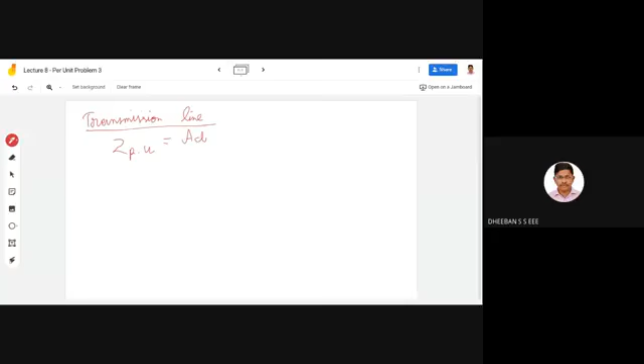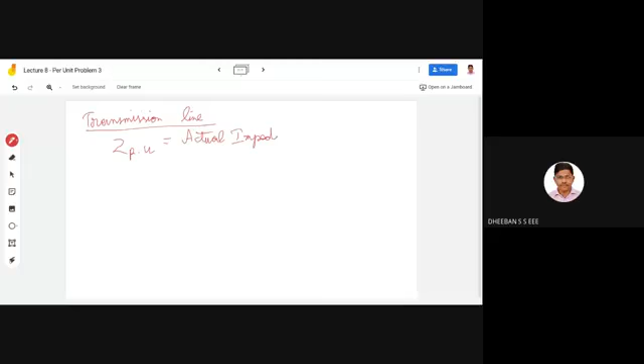So this is what with respect to your transformers. Okay, so we have finished all the 4 transformers, and now we will be moving towards your load side. Okay, before load side we will be seeing your transmission line. So afterwards we will be getting towards your load side. So for the transmission line, as you know, the formula what you'll be using is Z per unit is equal to actual impedance by your base impedance, since they have given you a reactance value. So actual impedance divided by your base impedance.